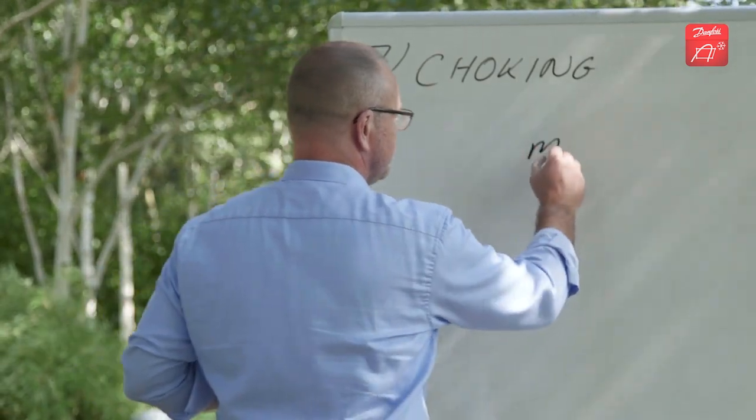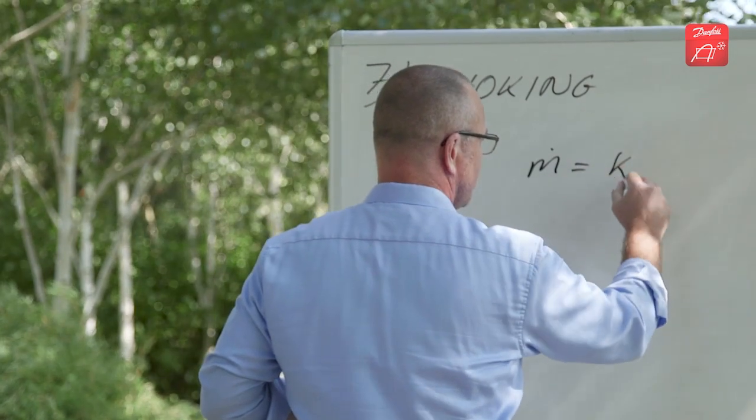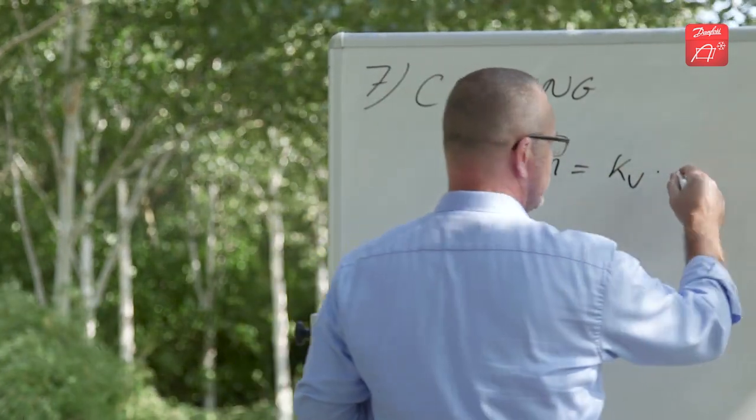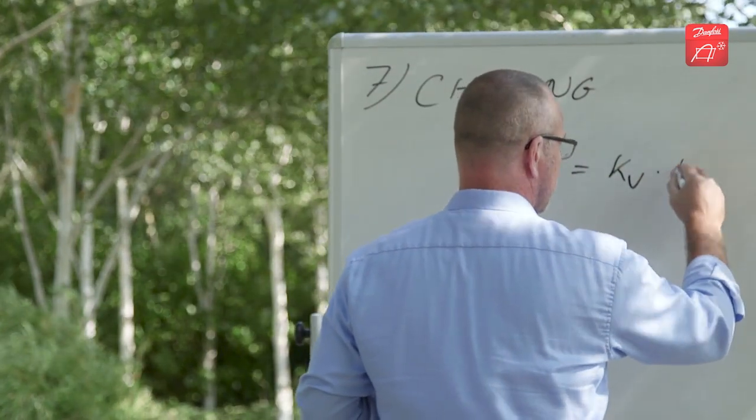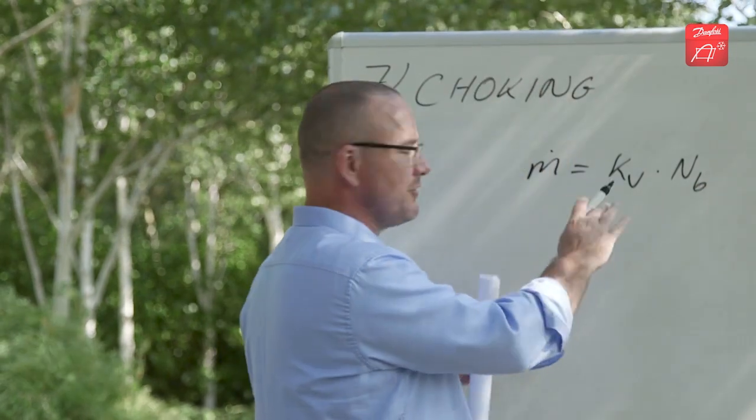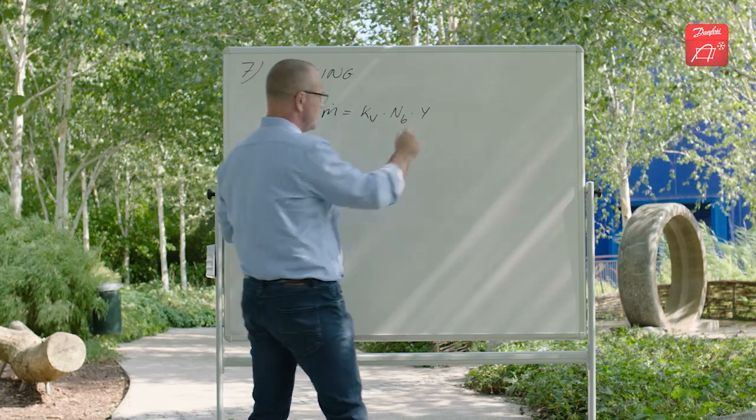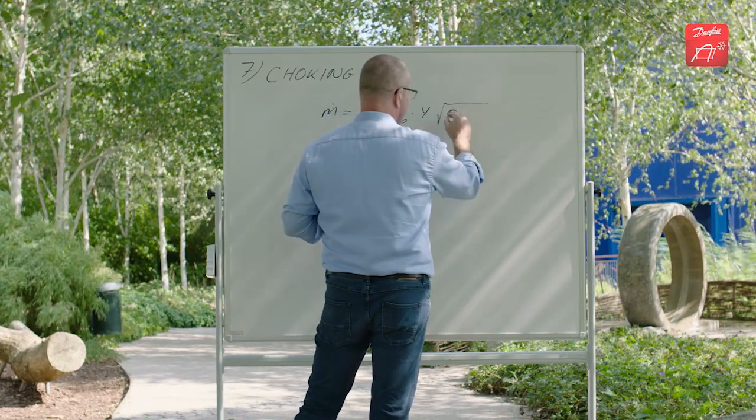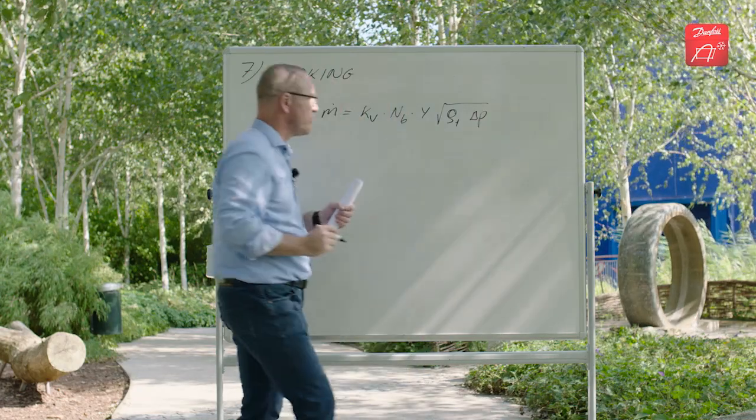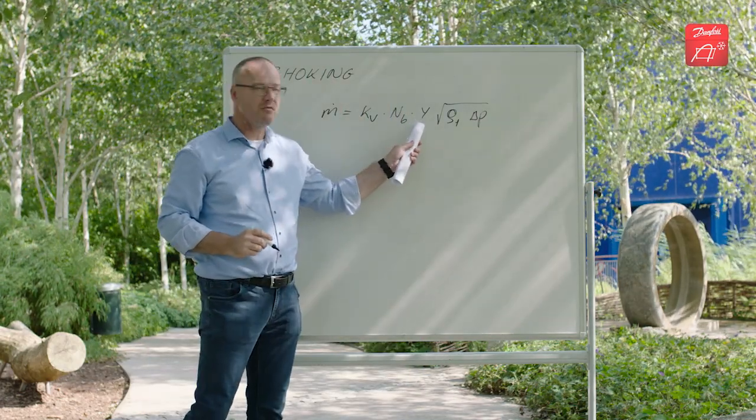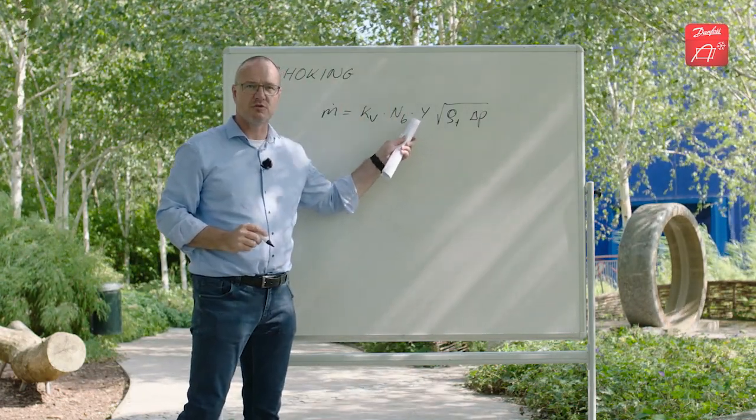The equation was the mass flow equal to kV value, the flow coefficient, times a constant taking care of units and stuff, times the net expansion factor and the square root of the density times the pressure drop. And for incompressible flow the net expansion factor was equal to 1.